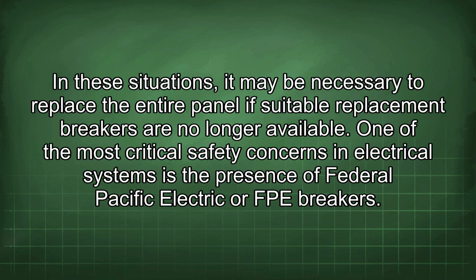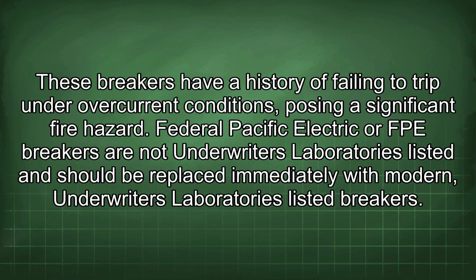One of the most critical safety concerns in electrical systems is the presence of Federal Pacific Electric or FPE breakers. These breakers have a history of failing to trip under overcurrent conditions, posing a significant fire hazard. Federal Pacific Electric or FPE breakers are not Underwriters Laboratories listed and should be replaced immediately with modern, Underwriters Laboratories listed breakers.